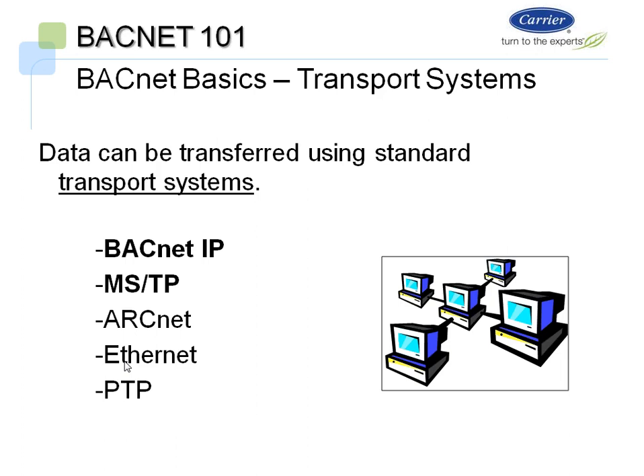Finally, the third rule we have here are transport systems, and it is basically just how you communicate physically, what type of wire you use or what type of protocol you use throughout the BACnet system. So the 5 ones that BACnet can currently do are BACnet IP, MSTP, ARCnet, Ethernet, and PTP. Each of these transport systems are readily available and used by many vendors, manufacturers. Currently, Carrier can only do BACnet IP and MSTP, but the majority of what you'll see out there is BACnet MSTP currently. However, the way BACnet is open protocol, standard protocol, it could use ARCnet, Ethernet, or PTP as well.